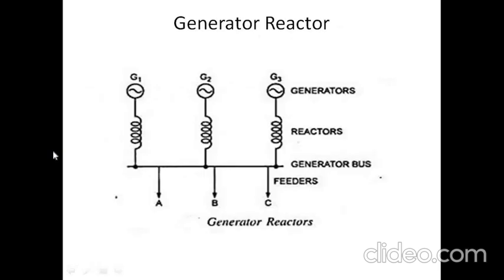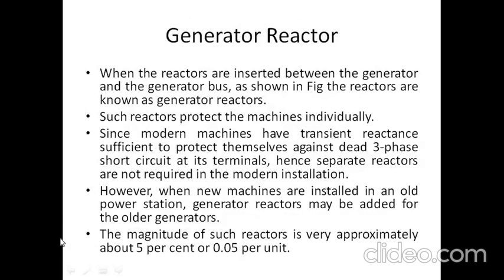When the reactor system is connected in series with the generator, it is called a generator reactor system. When the reactor coil is connected in series with the feeder, it is known as a feeder reactor. When reactor coils are connected in series with the bus bar, it is called a bus bar reactor system. In the figure, G1, G2, G3 are the alternators, and this is the generator bus bar. A, B, C are the feeders, and the reactor coil is connected between each generator and the bus bar.